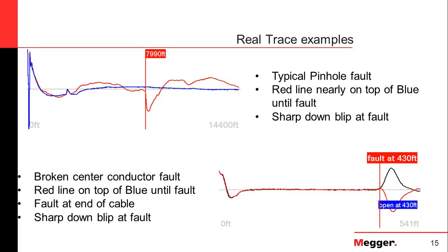So I would contend that your typical arc reflection shot, we haven't gone through the whole process, but typically you're doing these arc reflection shots pretty close to phase to ground operating voltage. It is an impulse, but I would contend that from a practical point of view, the arc reflection is not going to cause any additional damage to the cable.